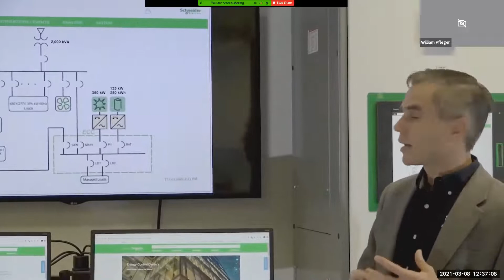And some other key loads, particularly associated with resiliency plans for shelter in place for a potential winter storm scenario. So we moved these loads into the ECC, and we brought over that otherwise stranded capacity of the generator. So that extra 200 kilowatts that the generator has to give is available to power these additional loads.